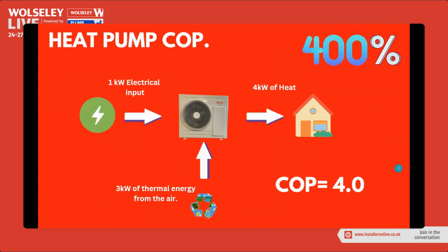In this diagram, we're taking 1 kilowatt of electrical input to drive a fan and a compressor inside our heat pump unit. We're actually stealing 3 kilowatts of thermal energy from the outside air. This heat already exists, even when it's -10 outside there are warm air particles in the air. We're compressing and condensing that and pushing it into 4 kilowatts of usable heat. So a COP of 400% efficient is really good.